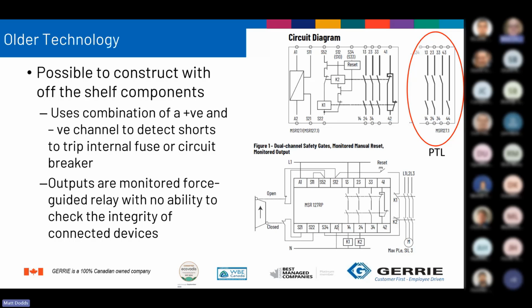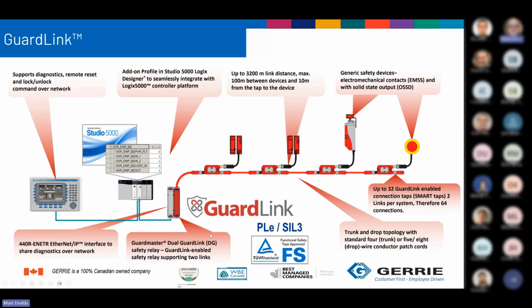And then, you know, there's also a model. So if you see the MSR in the example there, there's the MSR 127.1. If you look at it, the auxiliary output 43-44 was normally open versus normally closed. So I would use that on a power to lock type door switch application. So again, now I need two different relays, and then there was all the variations. So again, really cut down on my inventory by switching to the 440R.